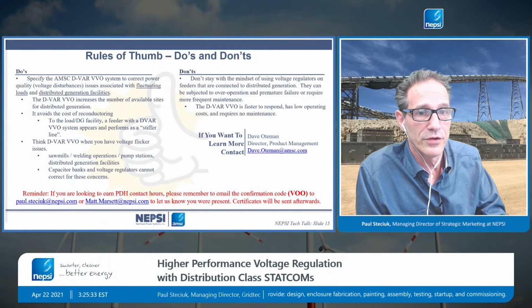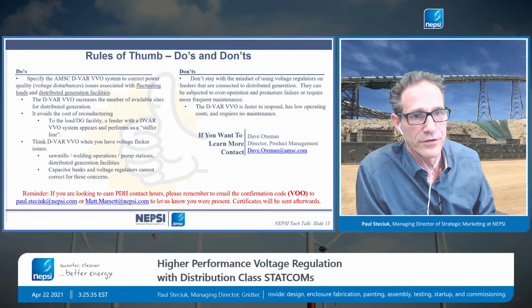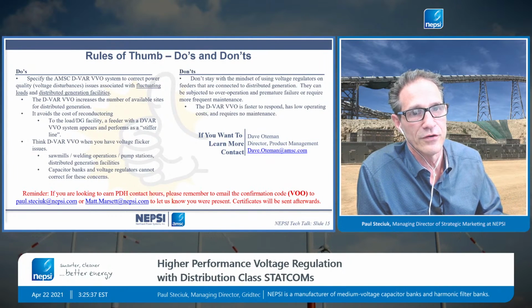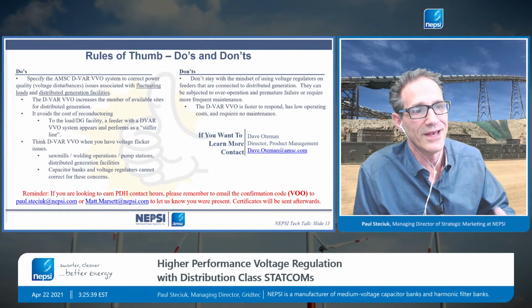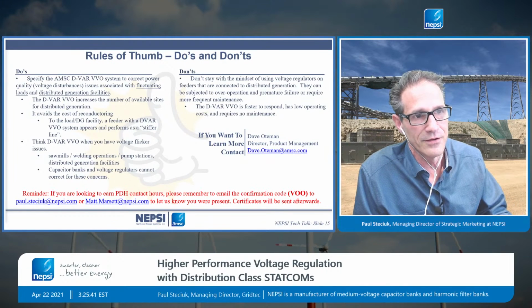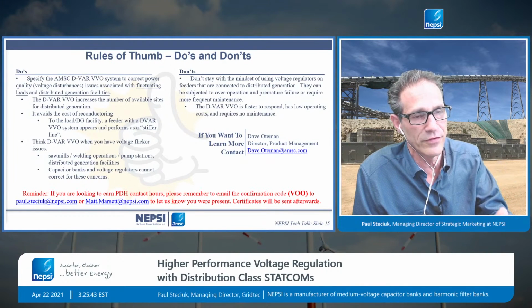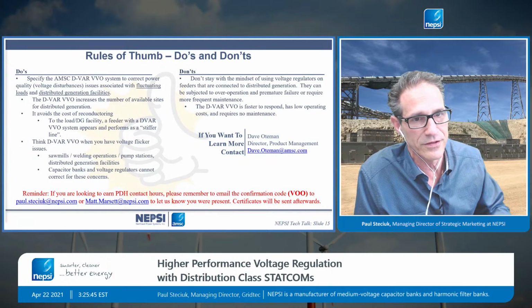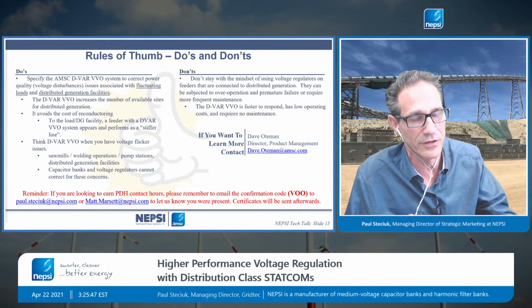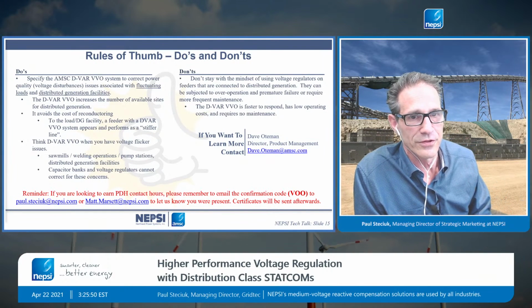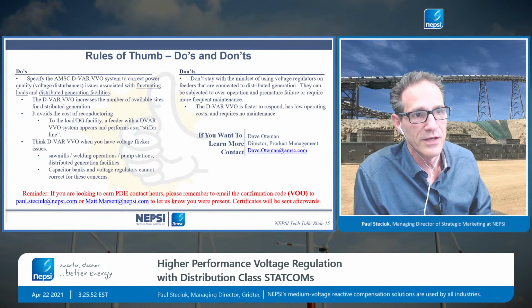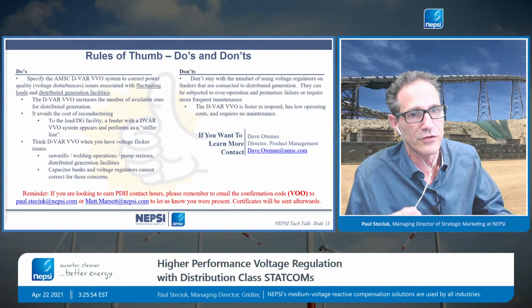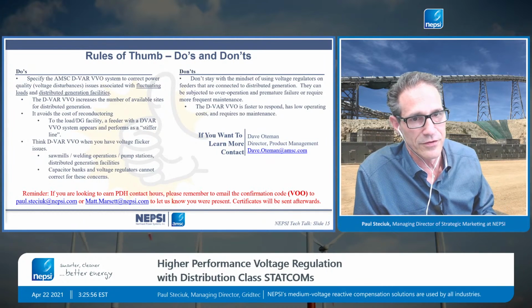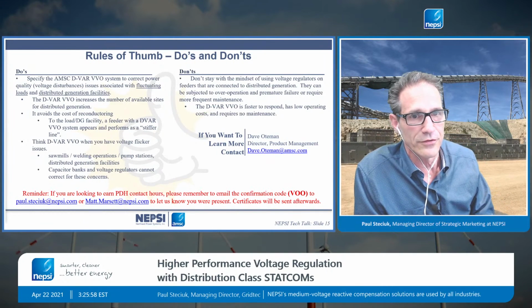To a load or a distributed generation facility, a feeder with a D-VAR VVO system appears and performs as a stiffer line, the same effect as reconductoring, which Dave covered in the presentation. So that's an interesting concept: avoid the cost of reconductoring by installing the D-VAR VVO system instead, which is much easier to do.